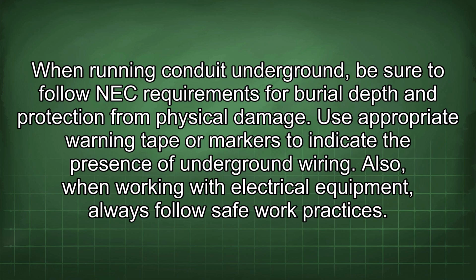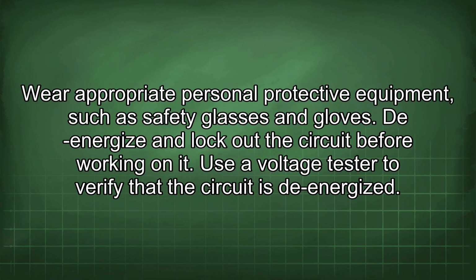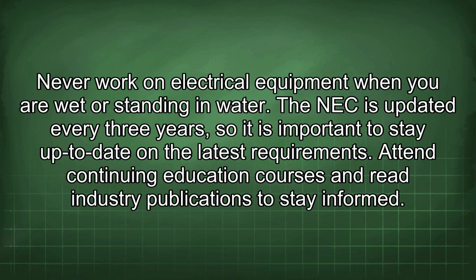Also, when working with electrical equipment, always follow safe work practices. Wear appropriate personal protective equipment, such as safety glasses and gloves, and de-energize and lock out the circuit before working on it. Use a voltage tester to verify that the circuit is de-energized. Never work on electrical equipment when you're wet or standing in water.